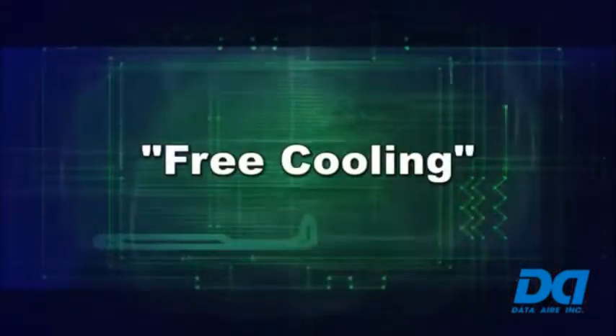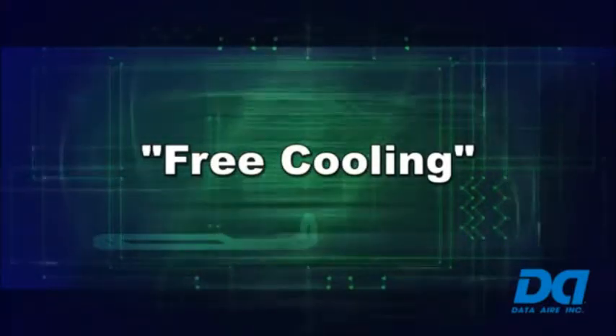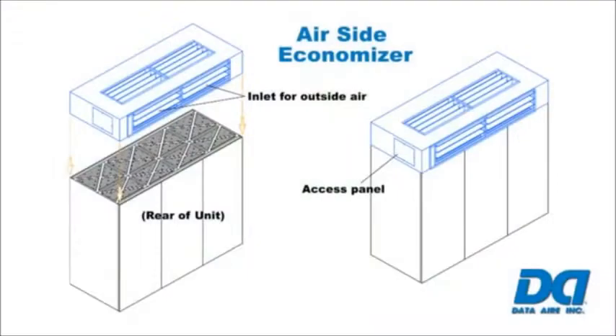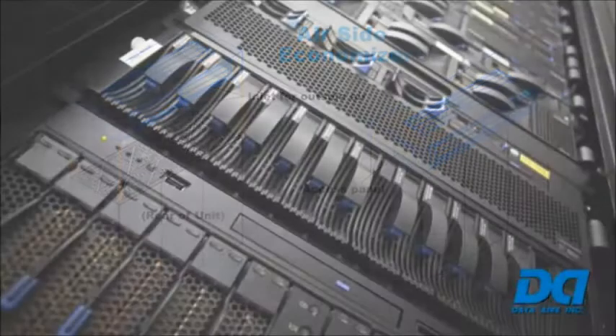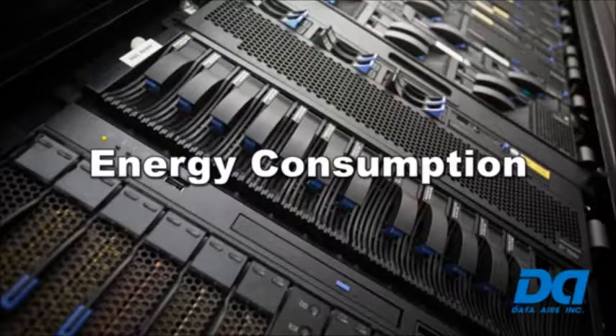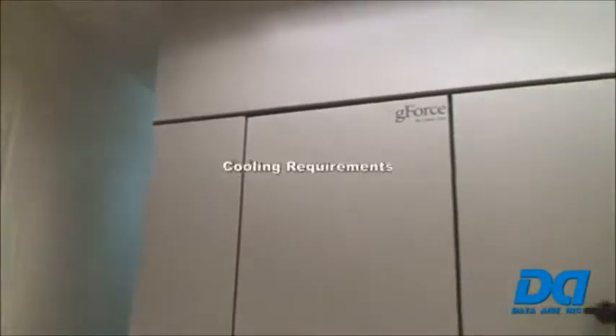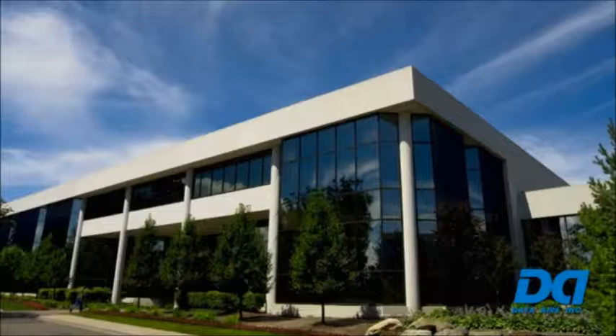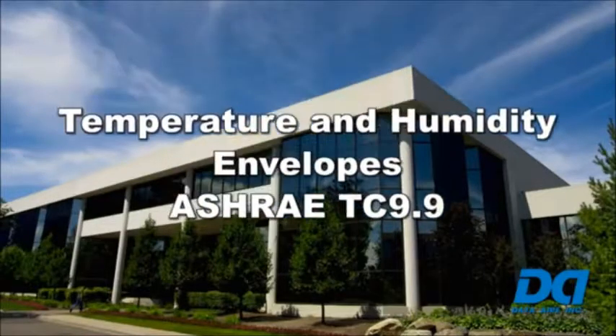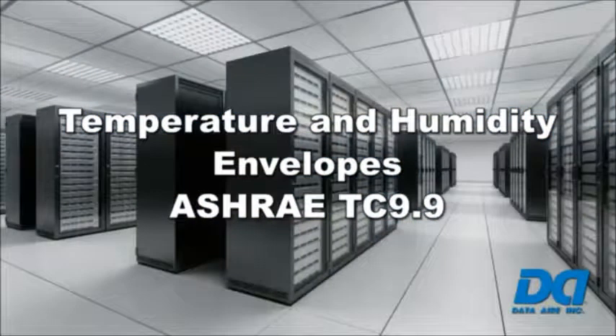Sometimes referred to as free cooling, airside economizers have been around for some time, but it's only recently they've become popular with data center designers and managers. This is due to the increased attention given to energy consumption by data centers and the significant portion of that energy consumption attributable to cooling requirements. Another factor is the recent expansion of temperature and humidity envelopes published by ASHRAE's TC 9.9 Committee for Data Centers, which has made the use of economizers more economically feasible.